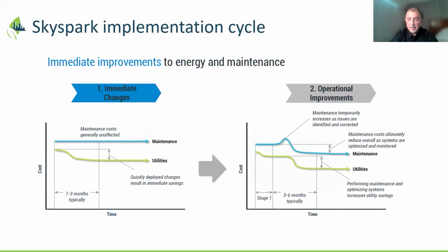So pumps running when they shouldn't, scheduling issues - that's the low-hanging fruit you should expect. What implementers thinking about analytics should look at is gaining more insight from the system, looking at established rules, and how the equipment is performing. You could have people comfortable in the space without realizing both heating and cooling are on at the same time, the chiller and boiler running simultaneously during shoulder seasons.